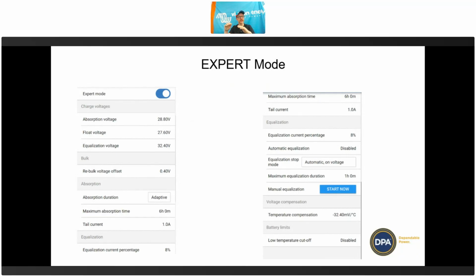The reason for that is, imagine you have some lead acid batteries. If you brought them all the way up to the absorption voltage, they're going to be gassing off and bubbling and things like that. You don't want to be doing that because you're going to dry them out. So once they've finished absorbing, they then get held at this lower voltage where they're still full, but they're not gassing off, right?